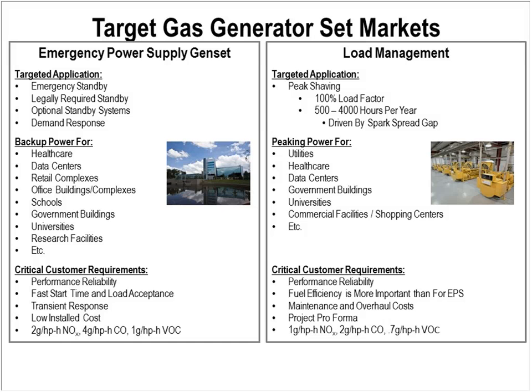Again, it'll give you excellent fuel efficiency. As you lower the NOx requirements, you will have a negative effect on the amount of block load that you can pick up at one time on those engines, but they are very capable of doing that. The gas engine in the standby environment will be classified as a continuous operating engine. So even though it's technically in a standby application, because of the way you rate a gas engine, with the limitations on detonation and on the temperature in the exhaust system, they are limited on exhaust and detonation, and so you do not reach a kilowatt level where you have a 10% overload.